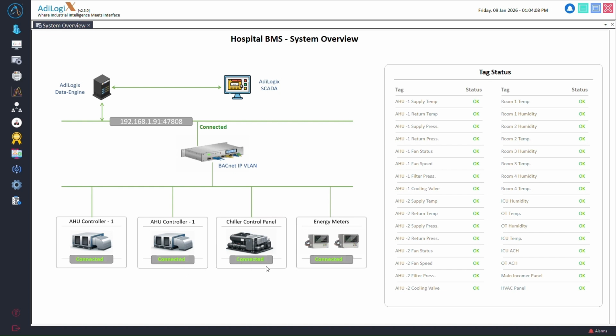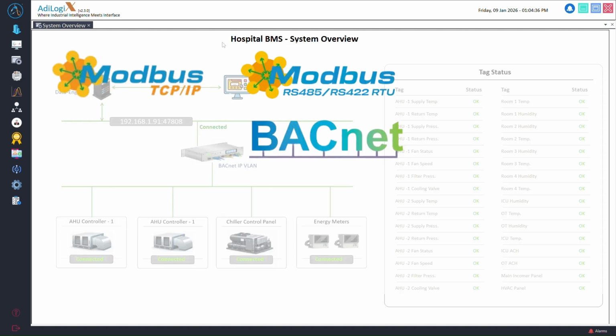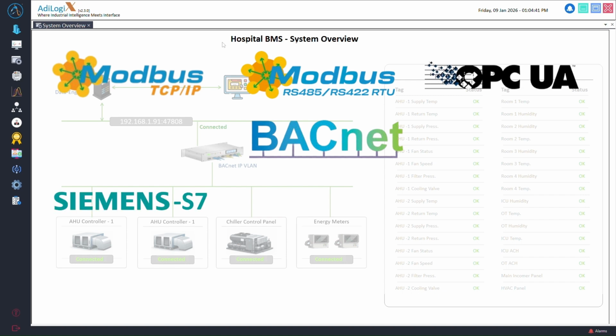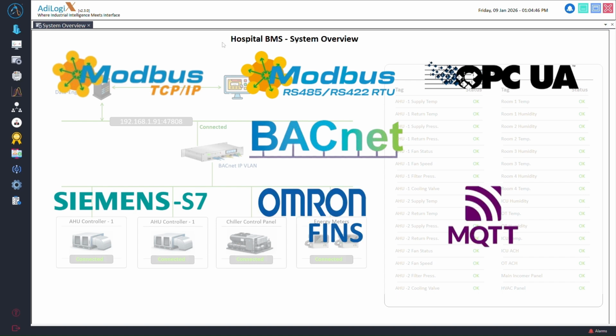On the right, the tag status panel confirms real-time data availability from every critical point. This eliminates blind spots. Operators know instantly whether data is healthy or at risk. While this system uses BACnet IP, AdiLogiX is built as a true multi-protocol platform. In addition to BACnet IP, AdiLogiX natively supports Modbus TCP/IP and Modbus RS 485, OPC-UA for enterprise and industrial systems, Siemens S7 controllers, Omron FINS PLCs, and MQTT.